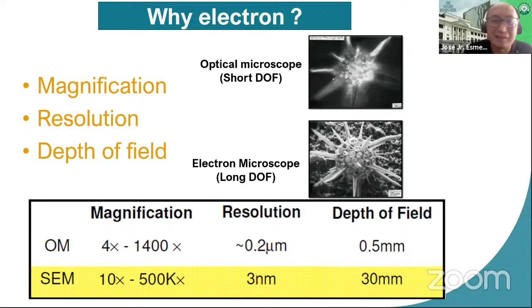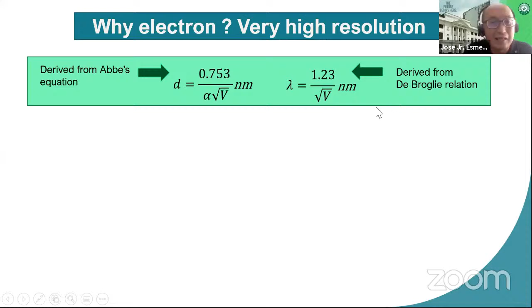Now, why electron? Why do you want to use electron? Because the resolution for electron microscope is derived from the Abbe's equation, which is related to the acceleration voltage. And the wavelength of the electron, because of its wave particle duality, is also related to the acceleration voltage. So these are derived from the scientists, Abbe and de Broglie. So just an example, a typical acceleration voltage for an electron microscope, 5,000 volts at 0.05 radian, okay, half angle of the objective lens. So we can see that the resolution for this type of electron microscope is about 0.2 nanometers, and its wavelength is about 0.0173 nanometer. Okay.